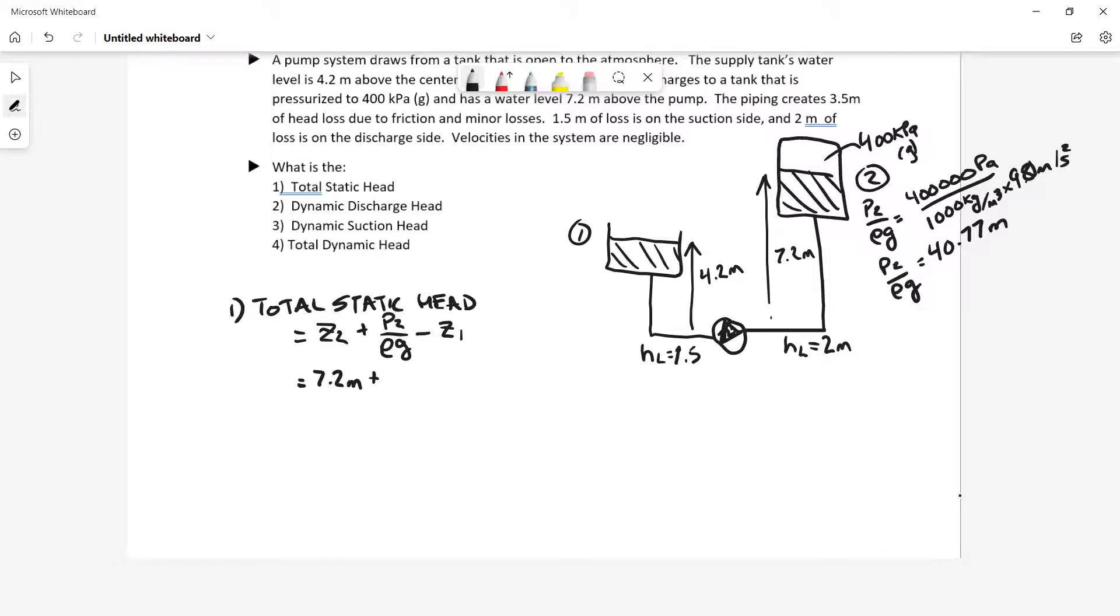And that ends up when I calculate that out to 40.77 meters is my pressure 2 over rho G, my pressure head in that supply tank, or sorry, the discharge tank. So 7.2 plus 40.77 meters minus 4.2 meters. And so this system has a static head of 43.77 meters.